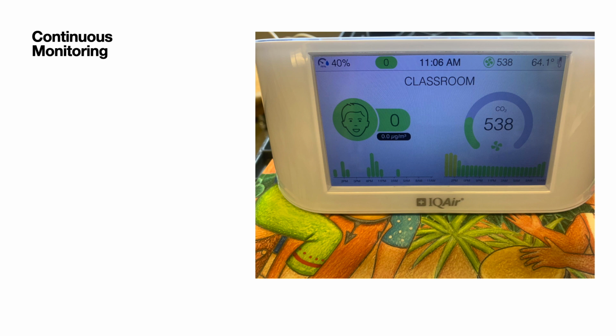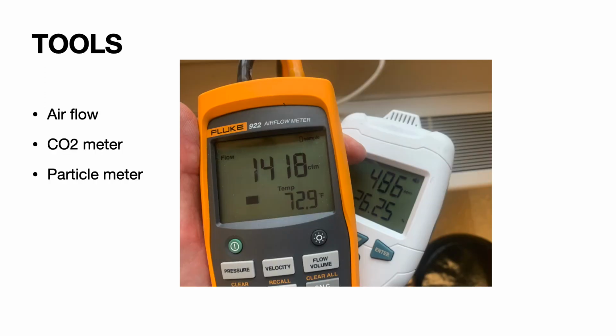And I was going to offer too, I'll show you at the end here, I have these very fast CO2 systems. If you have a problem classroom, or not problem, but you want to get your levels down, and you want to work with Dave or Mike, myself or Nina, we're happy to loan you one of these fast response for a day. And you can, titrate is the correct word. You can basically try things. We found opening the doors didn't work. Fans didn't work. Opening the upper window did, and you're going to see why here in a minute.